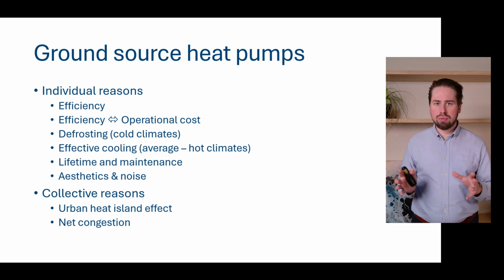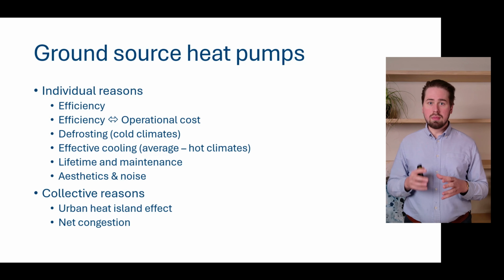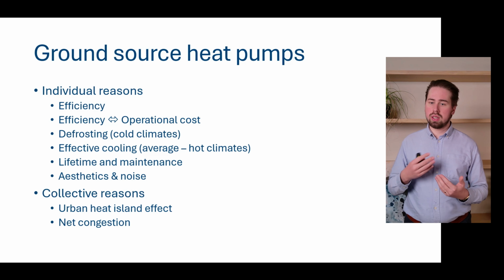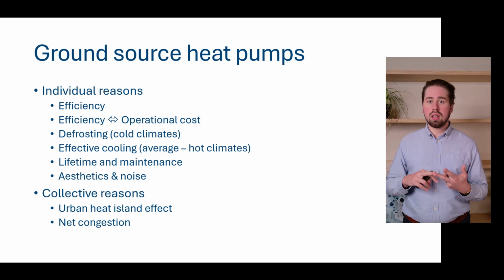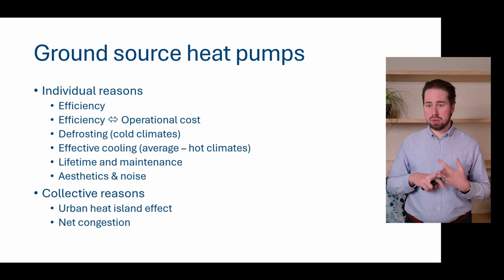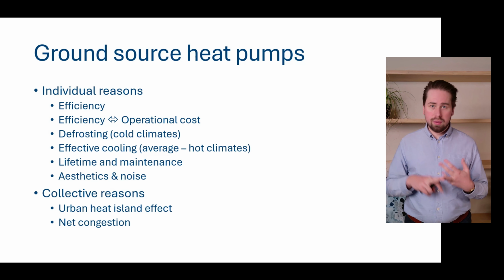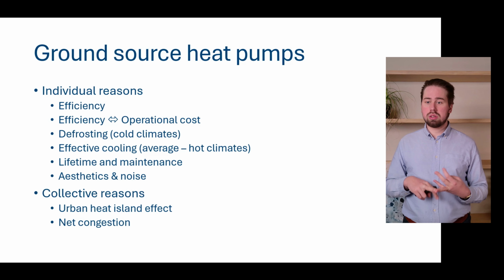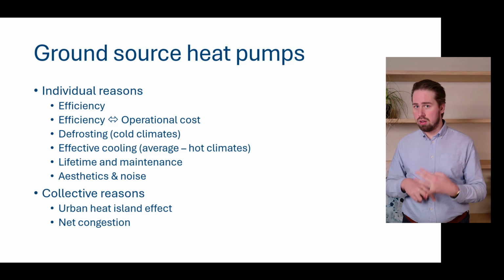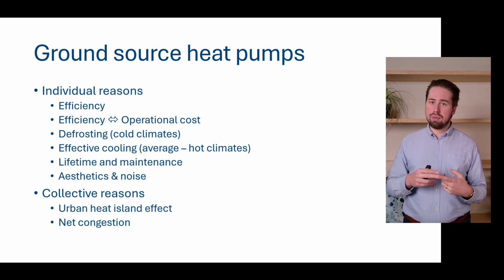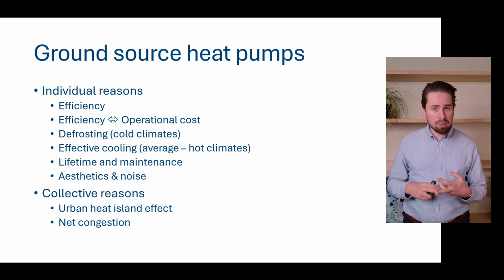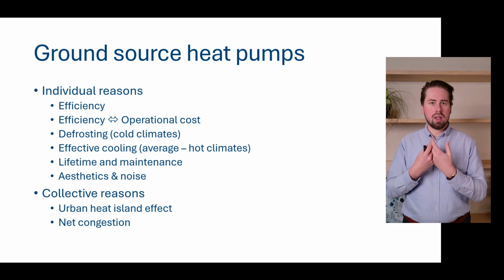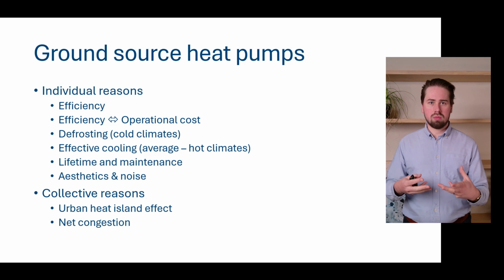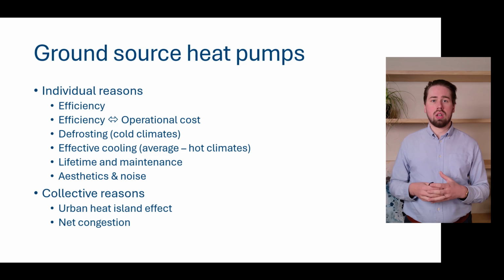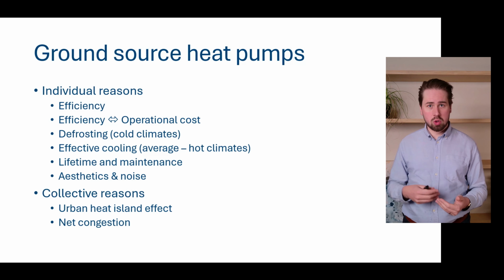Now, there are a couple of reasons for that. There are individual reasons. For example, you have efficiency versus operation cost. We have defrosting problems with air source heat pumps. You have effective cooling, lifetime maintenance, and aesthetics and noise. These are all individual reasons why you as a building owner would rather choose a ground source heat pump instead of an air source one.